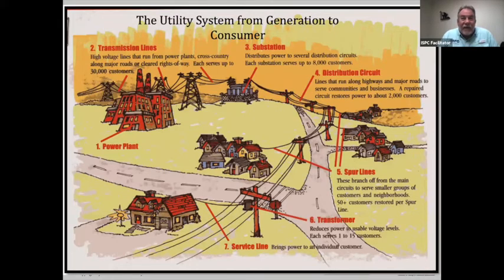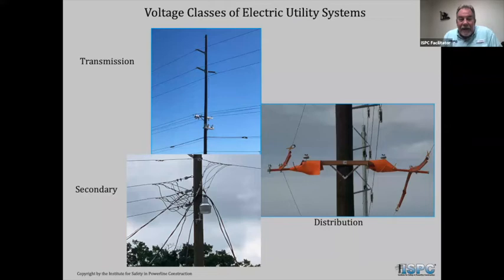We spend a little time trying to identify what is in the utility system from generation to the customer. So, I would spend a lot of time on this map, but you can see we produce electricity. It goes to a substation, goes out, reduces back down to a distribution voltage level, and then reduces down through a transformer to feed the house. Transmission usually looks a little bit taller, a little bit higher. Distribution on the right-hand side usually has a little bit smaller insulators to it.